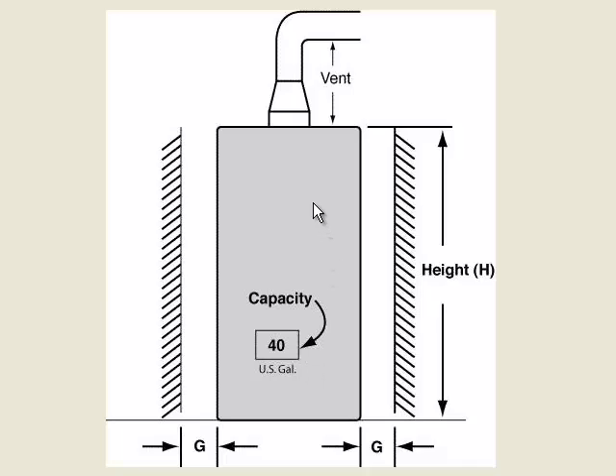The second thing that's also extremely important is what is the height from the top of the cylinder to the bottom of the vent. Most water heaters that I run into are gas fired, so they have a metal vent at the top. We want to know the distance between the top of the water heater here and the bottom of where the vent goes horizontal.